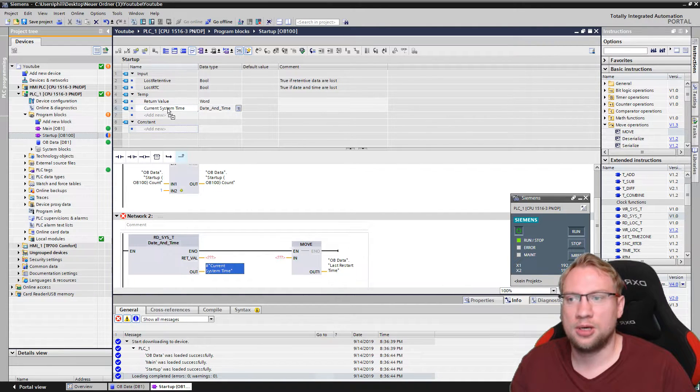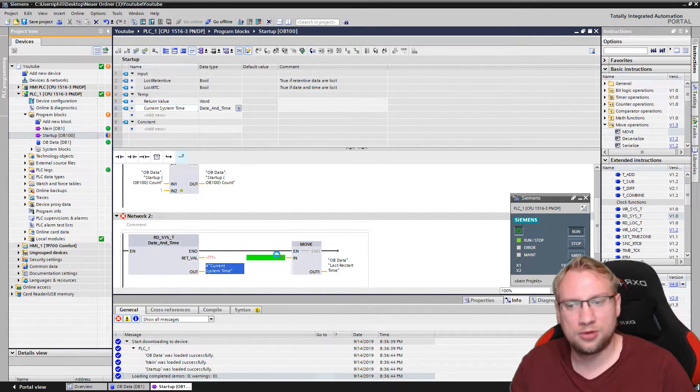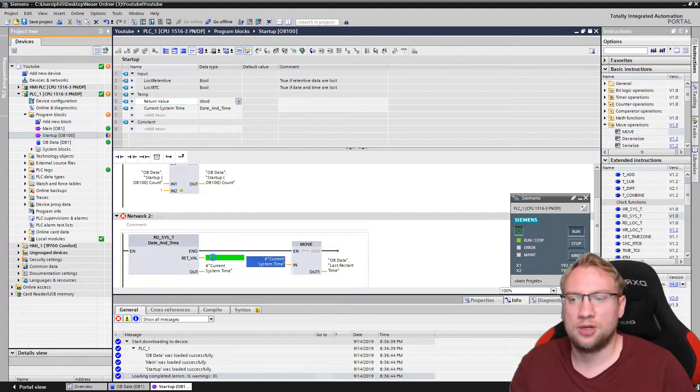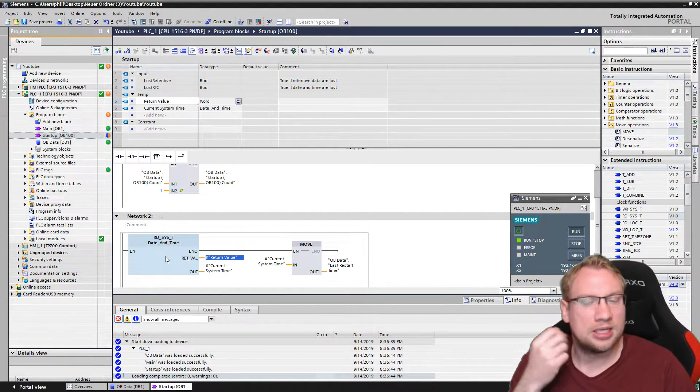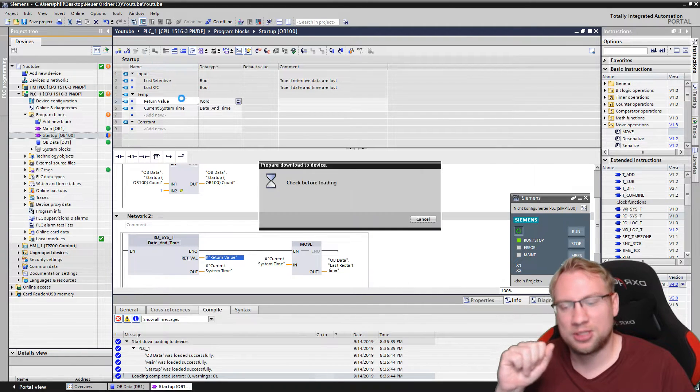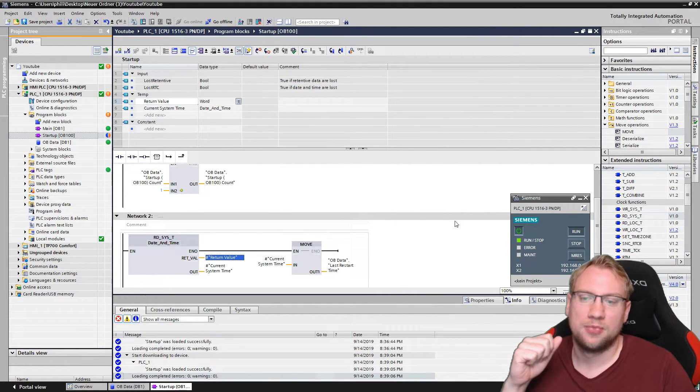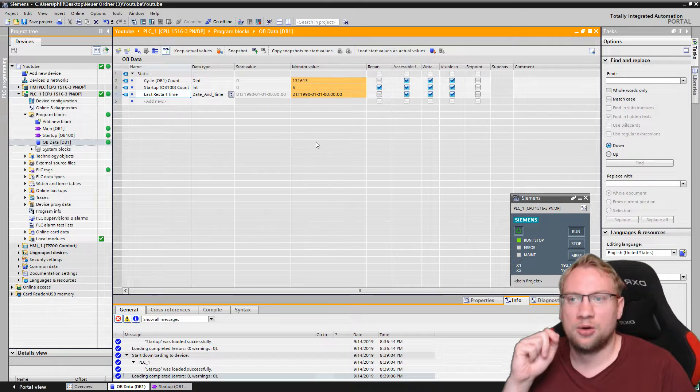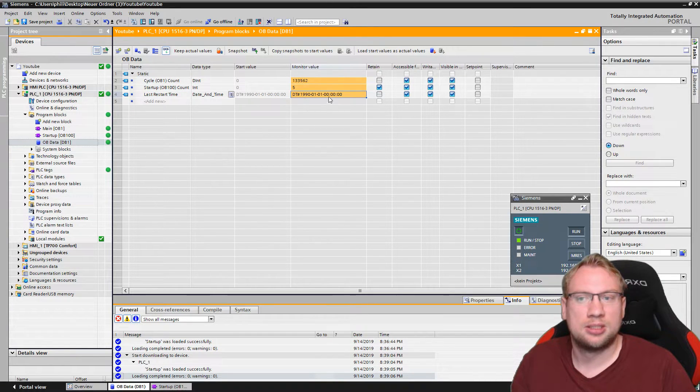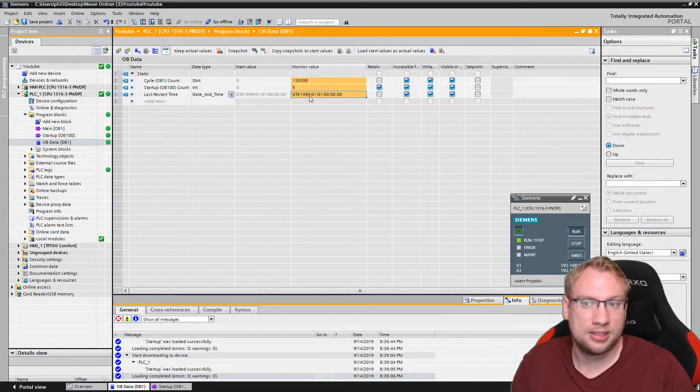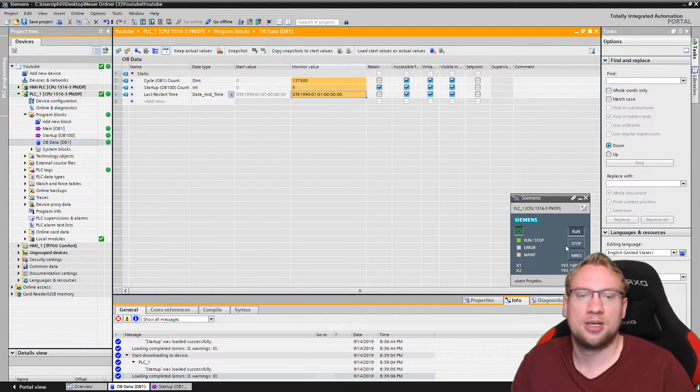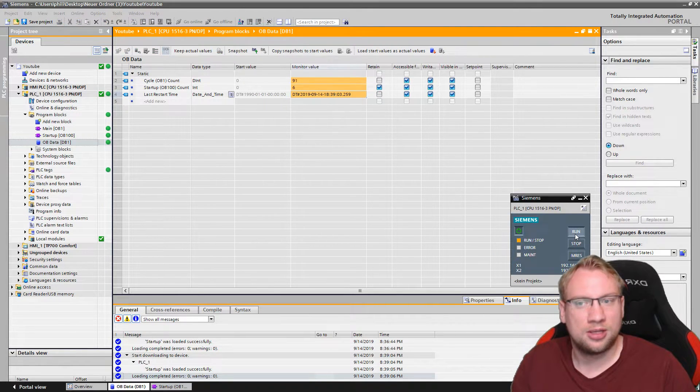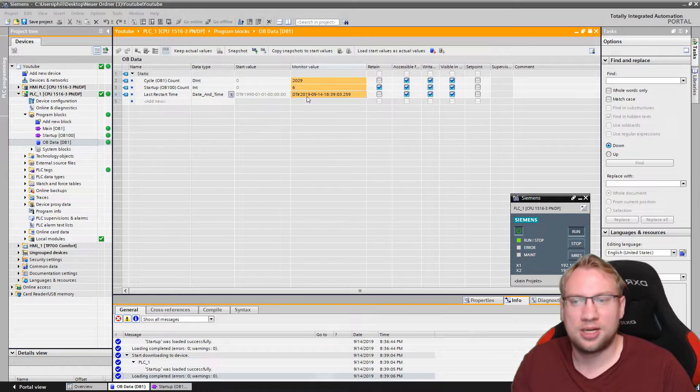Current system time, which is in date and time. So I can just take those two. One goes to the output, one goes to the input of our move instruction. And the return value, it needs the return value because it's a function. Functions need to have all the inputs and outputs connected that are there. So if I download now, I go in my OB, you see this is still set to 1990. That's my last startup time. I will need to stop and run the PLC, and you see this is the current time.